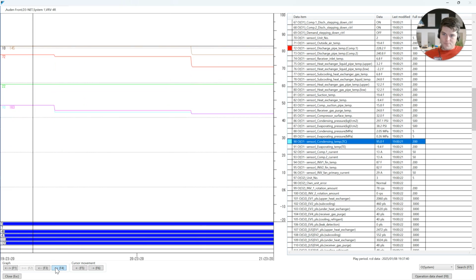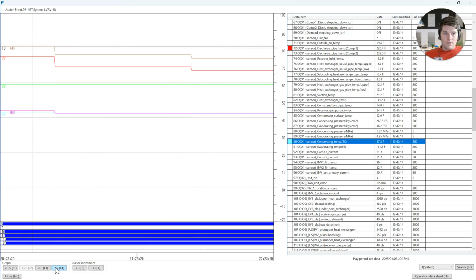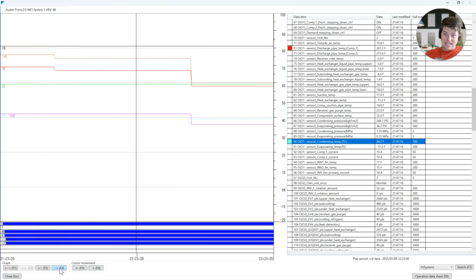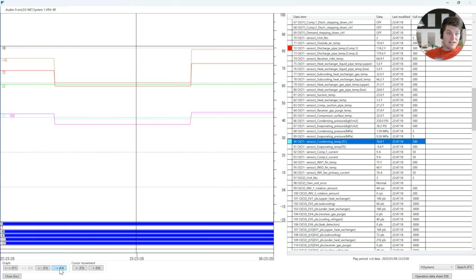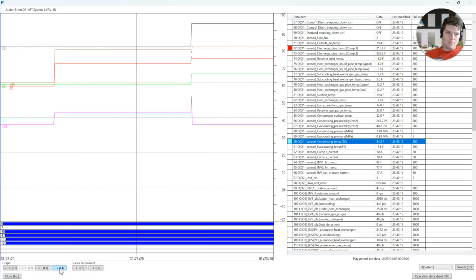So let's move on. Again, I'm looking at one thing. What am I looking at? I'm looking at discharge superheat. So because of that, we know this is 145. It kind of stays in the same range. 120, I would say that this number is, just by looking at it. And it stays high. And it changes, but does it really change? No, the numbers go lower, but they stay about the same amount apart, right?